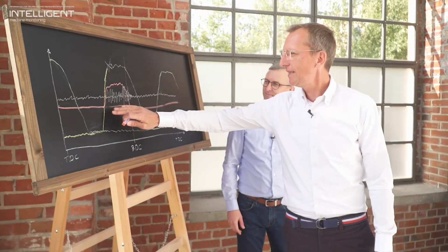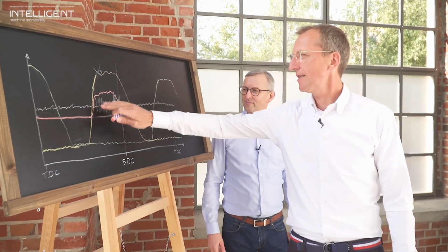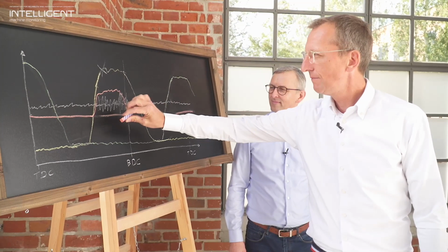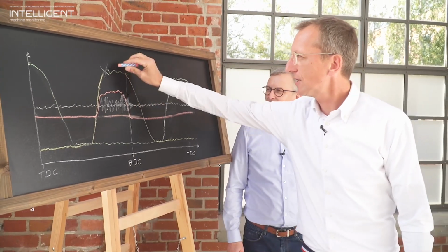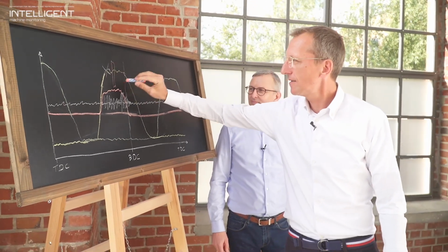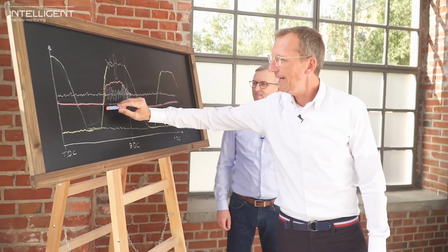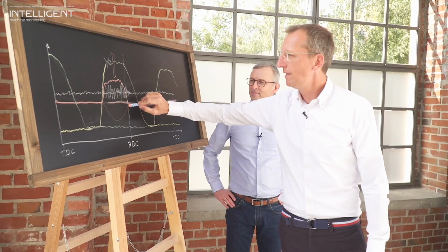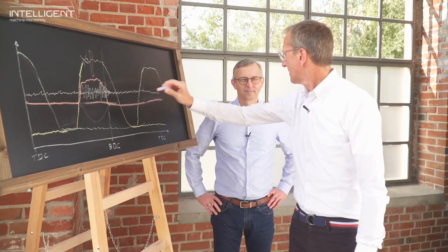May I ask a question here? What worries me a little bit is that the signal for the rod position goes up. What worries me is because the measuring sensor sits above, so the measuring value itself should go down and not up. How does this come?